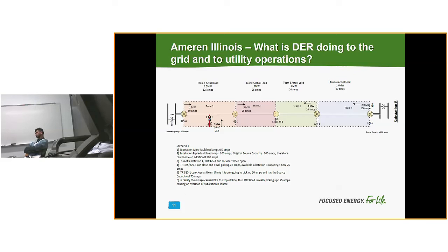Okay, so how does DER impact that? Let's go through a real scenario where you would have a fault and see what the 2 megawatt solar is doing in that case. If you look here, substation A's pre-fault load was 50 amps, so I am serving 50 amps on recloser 325-0. Substation B's pre-fault load is 100 amps, and its capacity, meaning the total amount of amps it can handle, is 200, right? So I can handle an additional 100 amps. So far, so good? Okay.